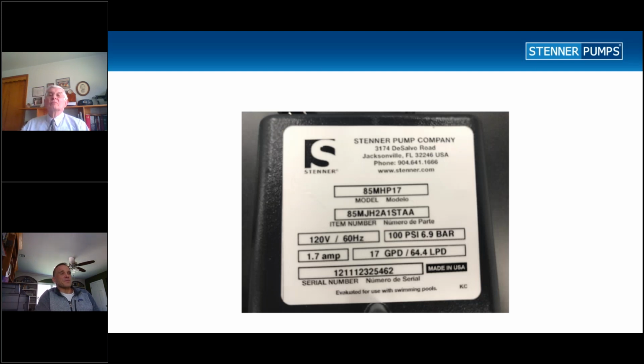To help you identify the pumps, and this is something that comes up often, if you call into our tech support line or if someone calls me, what we're going to ask is, what is the model number on the pump? What the model number is going to tell us here is the gearing. If we look at that top number, the 85 MHP 17, what that's telling me is that this pump has an 85 tooth gear set. And the 17 represents a 17 gallon per day max output flow. In this case, that could be achieved with an 85 series pump with a number 2 tube.